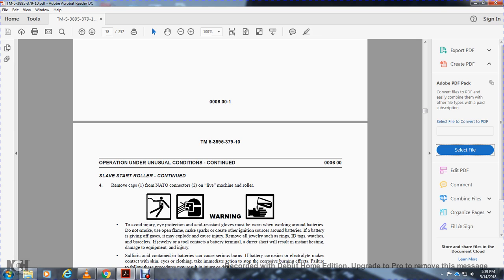To avoid injury, eye protection and acid resistant gloves must be worn when working around batteries. Do not smoke, or allow open flame, sparks, or any ignition source. Battery gas may explode and cause injury. Remove all jewelry, including rings, ID tags, watches and bracelets, and do not let tools contact battery terminals.